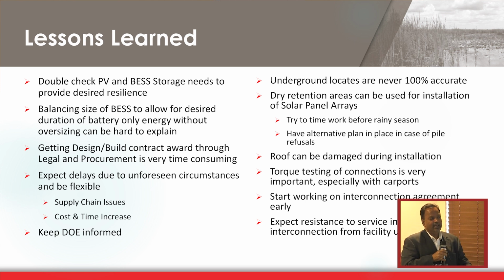Many times people ask, why just 3 hours? Why not 3 weeks? Well, the answer is you'd have to put a whole lot of batteries out there, and the stored energy would just be sitting there, not being used. The cost would be tremendous, and your batteries wouldn't function optimally, because you want the power to be recycling in the batteries. So the balance is 3 hours minimum backup with the BESS.